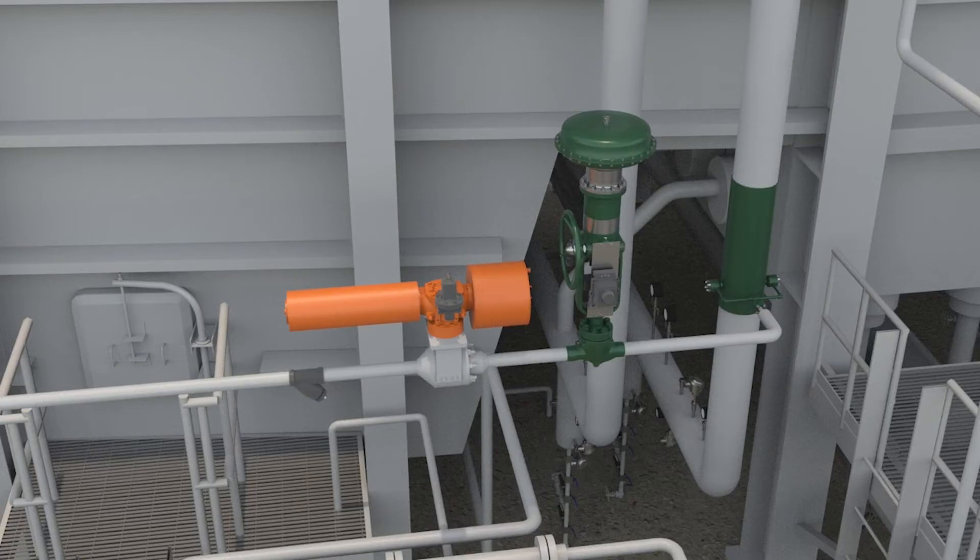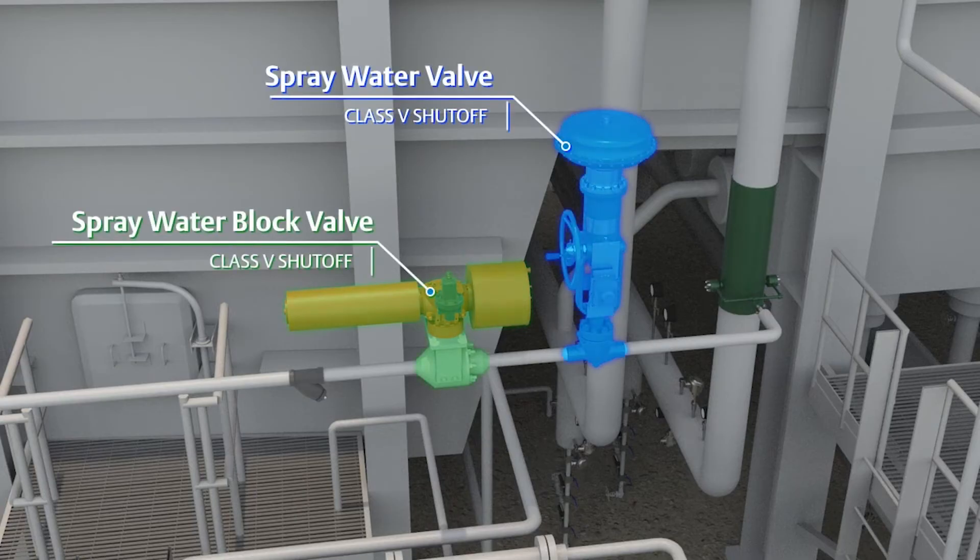It is important that the spray water and block valve shut off tightly, so that water does not leak into the steam line when it is not required, causing potential damage from thermal shock or efficiency losses from operating below steam temperature set point.